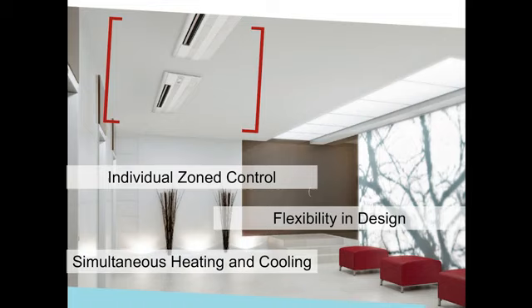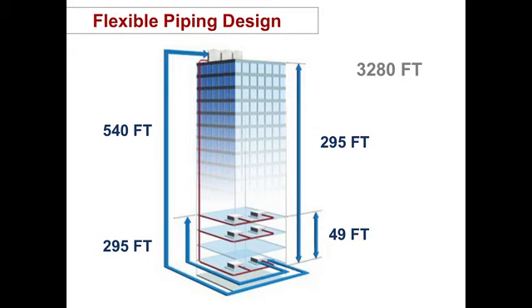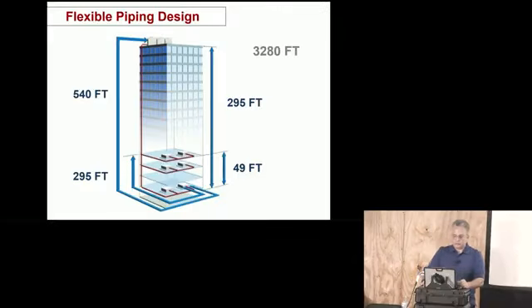The other thing about the flexibility in design is that you can choose whatever different models are available. So in this case, in this photograph, we're looking at the one-way cassette. But as we'll go over, there are a number of heads and sizes. And then simultaneous heating and cooling. So this is just a generalization, this is not from any one manufacturer, but typically speaking, you can have maybe a combined 3,300 feet of piping on a single system.